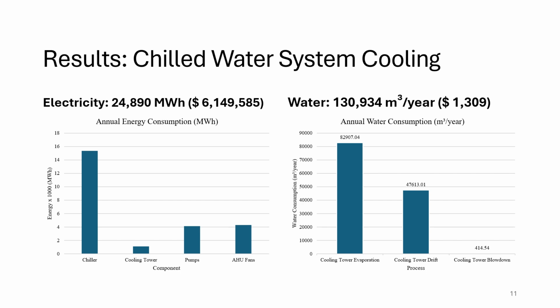The following slides analyze the results for the simulation of the various cooling systems. This slide analyzes when only the chilled water system is used for cooling. It shows that an annual electricity of 24,890 megawatt hours is used, costing over $6 million. Most of the energy is used by the chiller, followed by the air handling units and the pumps, with the cooling tower consuming the least. The system also uses over 130,000 cubic meters of water a year, costing $1,300. Most of the water is lost due to cooling tower evaporation and some due to cooling tower drift and cooling tower blowdown.